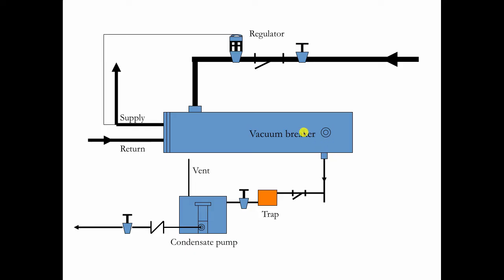So this is when we've got a vacuum breaker and a steam exchanger and everything is pretty simple here. Let's make it a little bit more complicated because what's going to happen if we don't get the water out of that shell, it's going to get hit with water hammer because the water will lay inside the shell and the next time the steam enters, it's going to take that water and bounce it off the back of that shell. It's going to turn around, it's going to hit the tube bundle and put holes like that in your tube bundle. And that happens all the time.